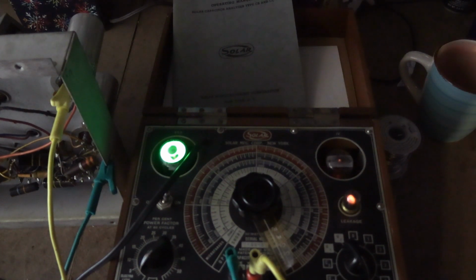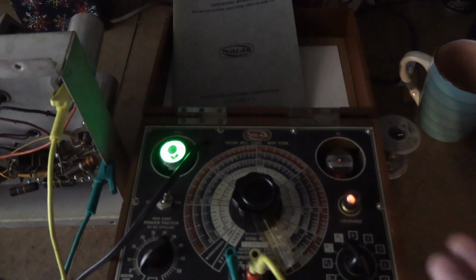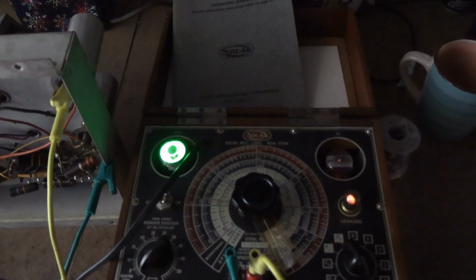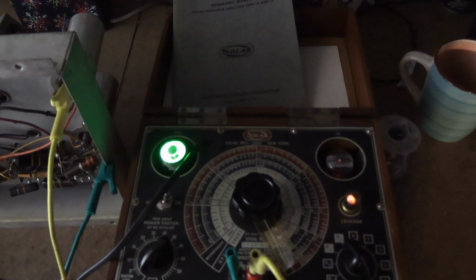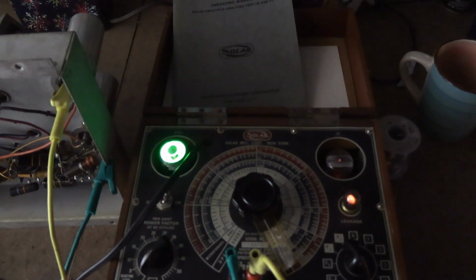So what does that mean? It means this cap, over time, would get a little warmer inside. First off, the fact that it's leaky at all is an indicator of health - it means it's degrading inside, and it may very well continue to degrade, because it'll start to get warm inside. That leakage current is going through the capacitor, acting like a resistor - there's current flowing through it. What happens when you have current flowing through something? It starts to get warm. That will accelerate the deterioration. It may take months, years, many hours of operation.